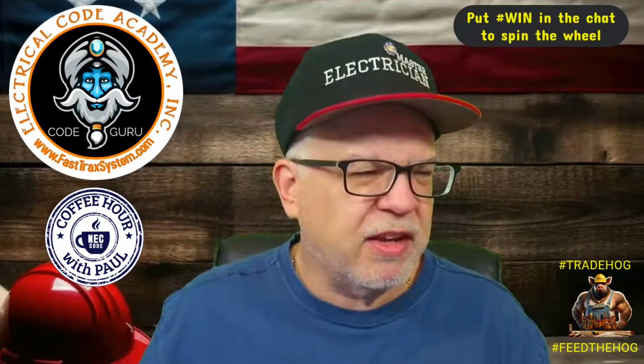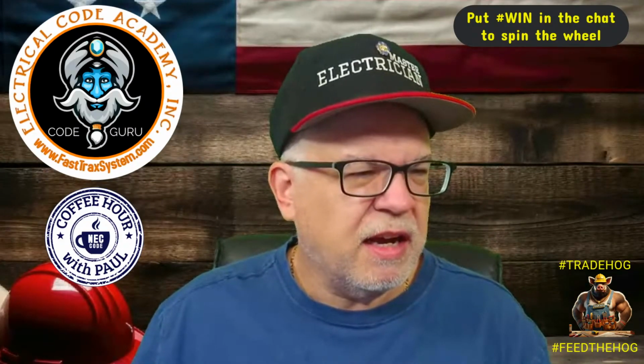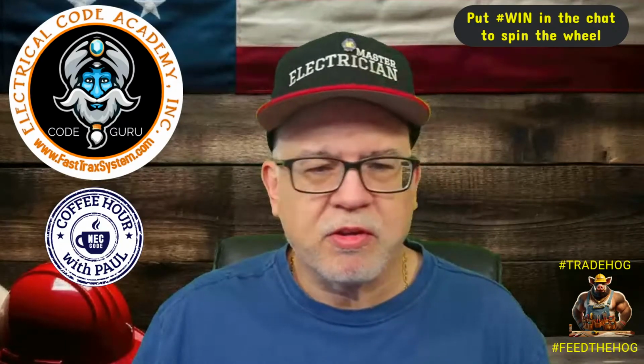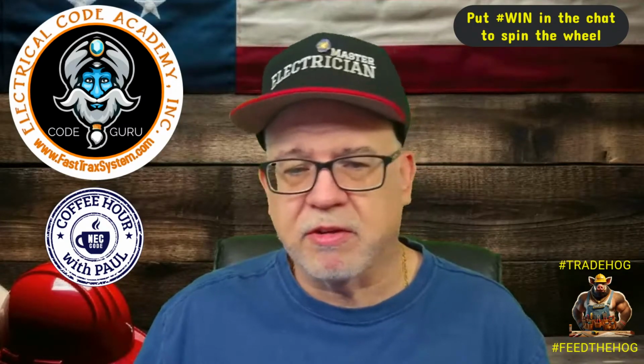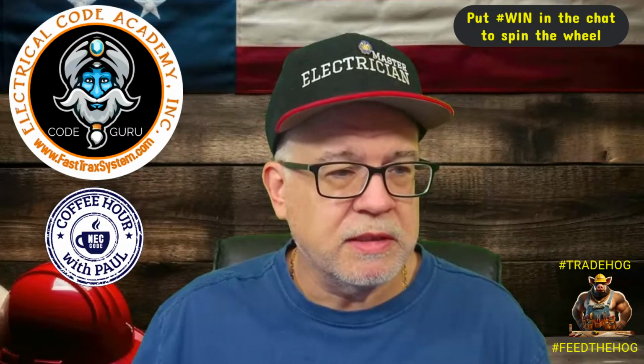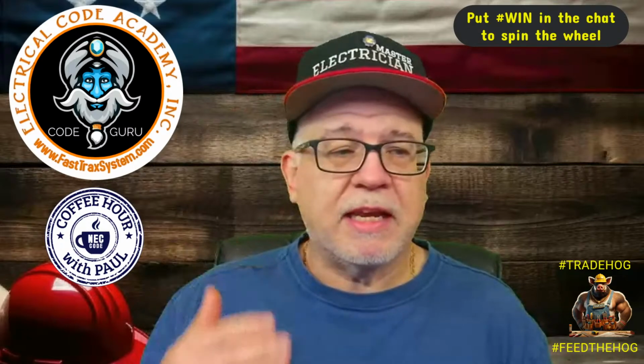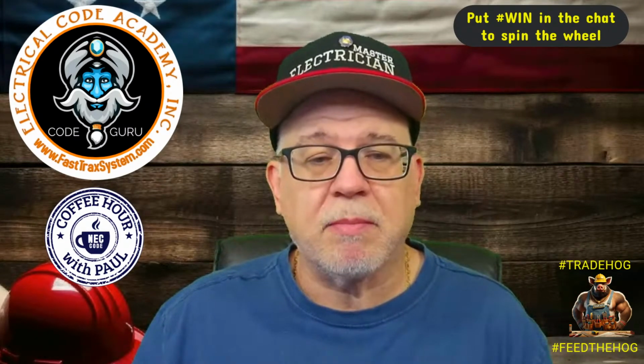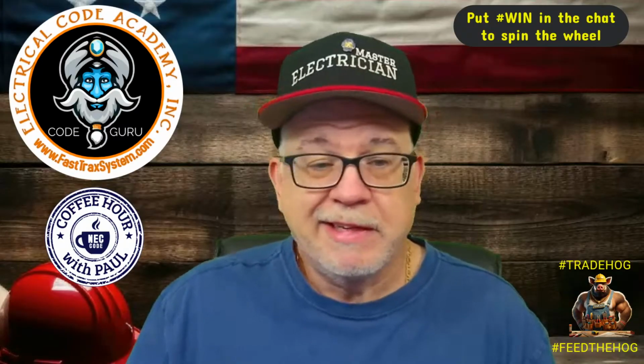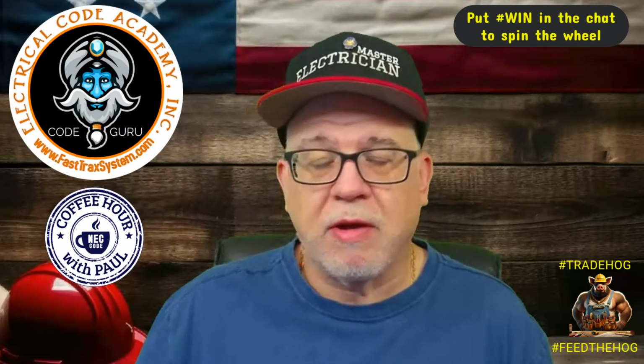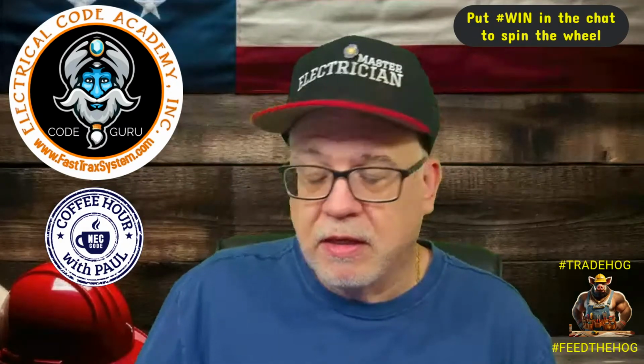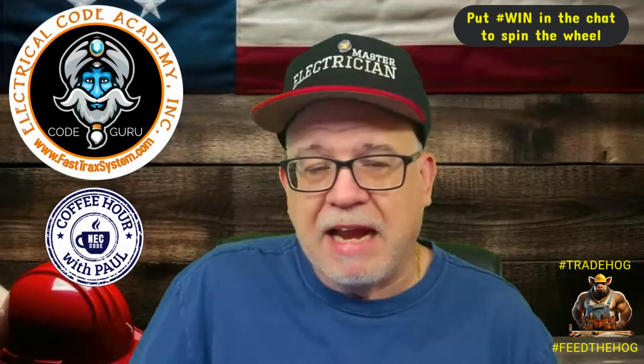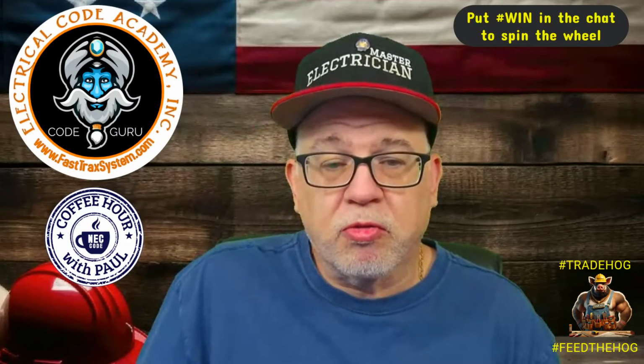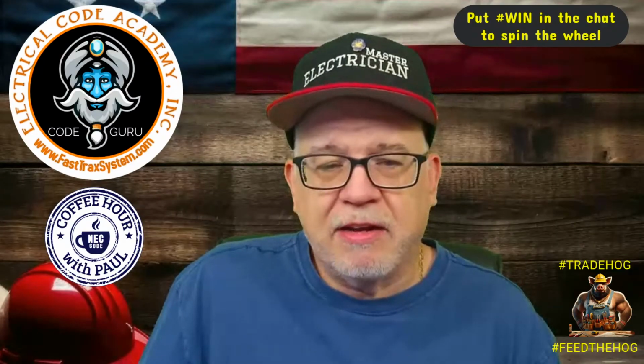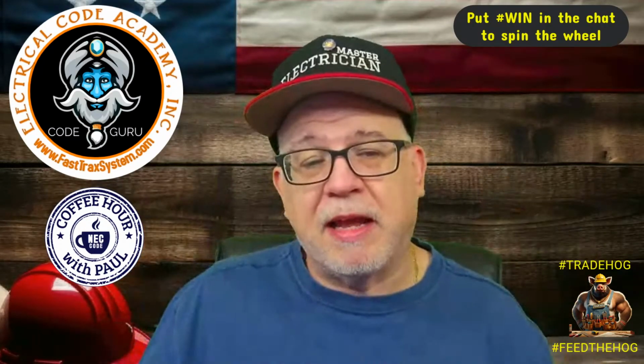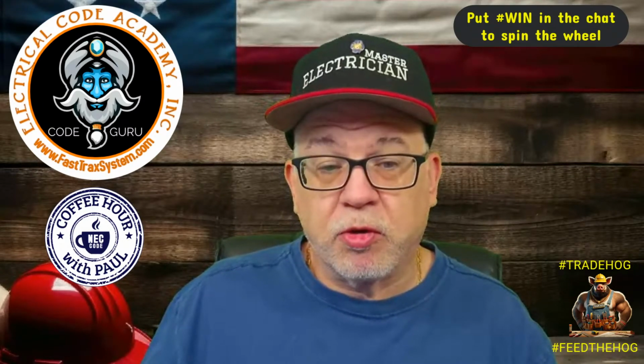Let me know. I will tell you, Doug sent a question in here about sizing MV. I can be honest with you, Doug, I've never seen that on a master's exam, never. And I helped write the Texas exam, so I've never seen it. Neutral loads: calculating the neutral is a matter of understanding what your maximum unbalanced load is. So whether it's medium voltage or regular, it's irrelevant. It's all about what the neutral load is, and you have to understand how to do a neutral load calculation. That's it. If the question tells you a value for the neutral, then that's what you use. But you've not given enough information to confirm or do any type of calculation for MV, medium voltage applications, for a neutral calculation.